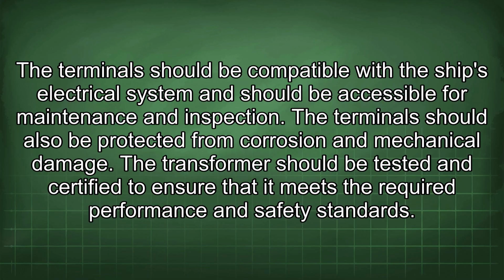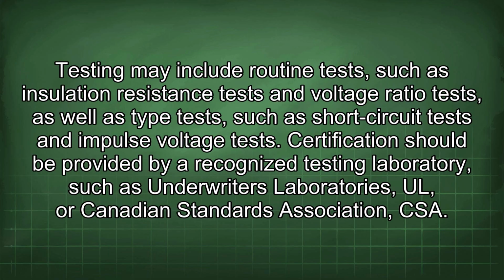The transformer should be tested and certified to ensure that it meets the required performance and safety standards. Testing may include routine tests such as insulation resistance tests and voltage ratio tests, as well as type tests such as short circuit tests and impulse voltage tests. Certification should be provided by a recognized testing laboratory such as Underwriters Laboratories (UL) or Canadian Standards Association (CSA).